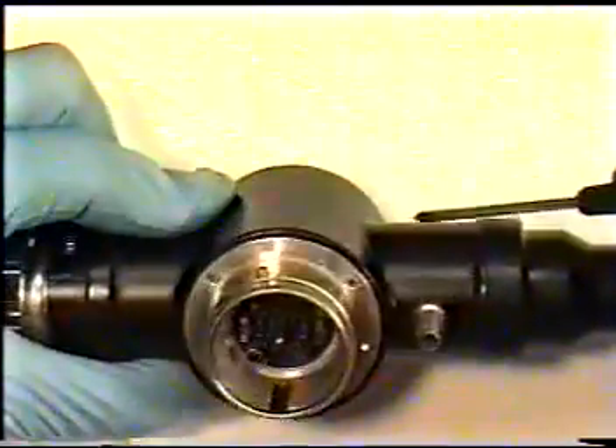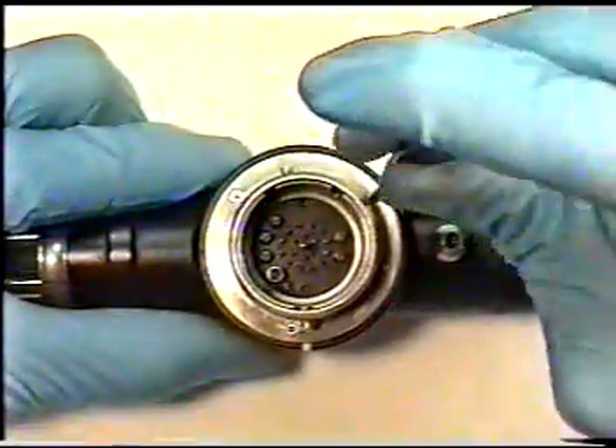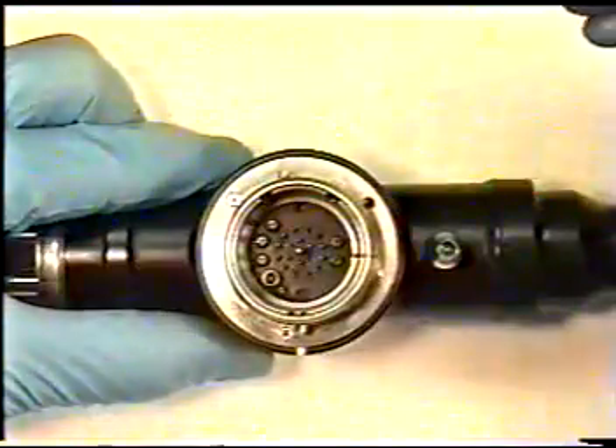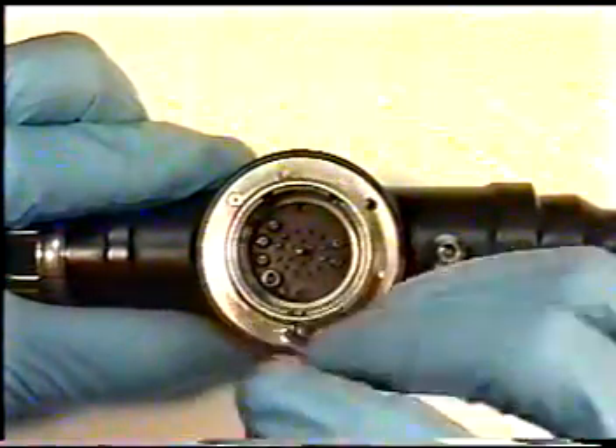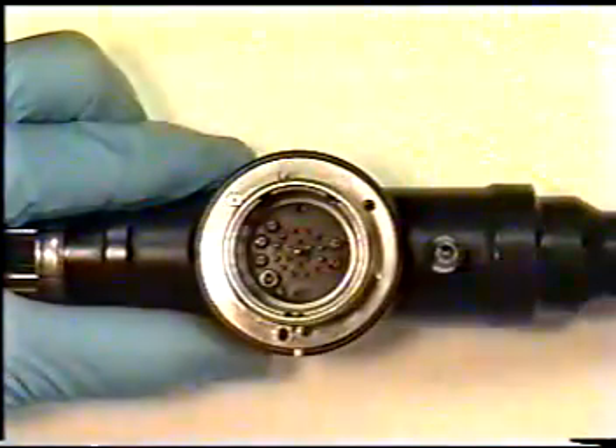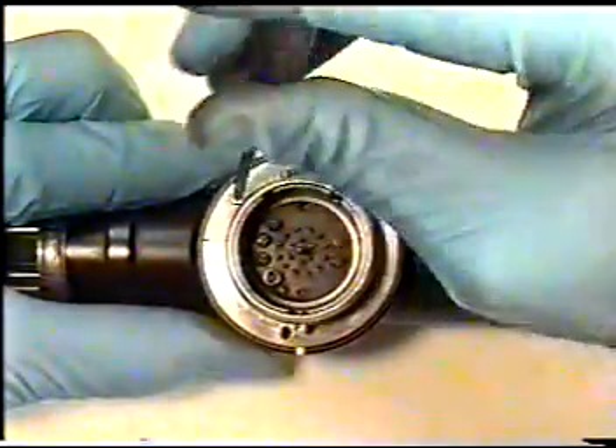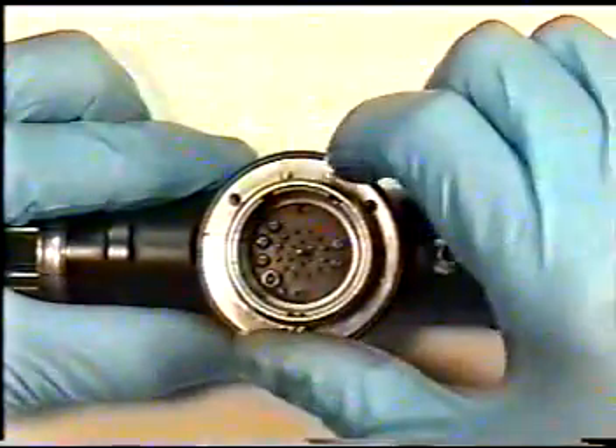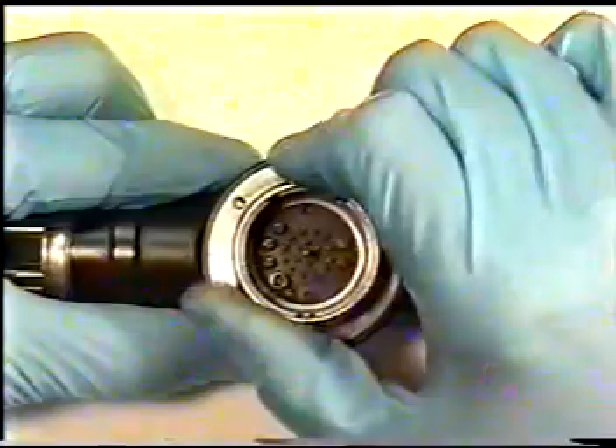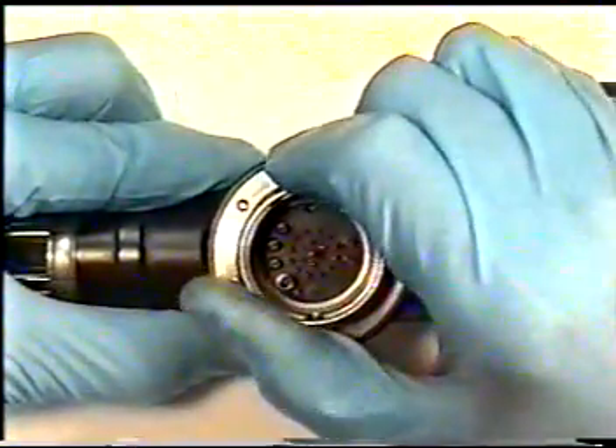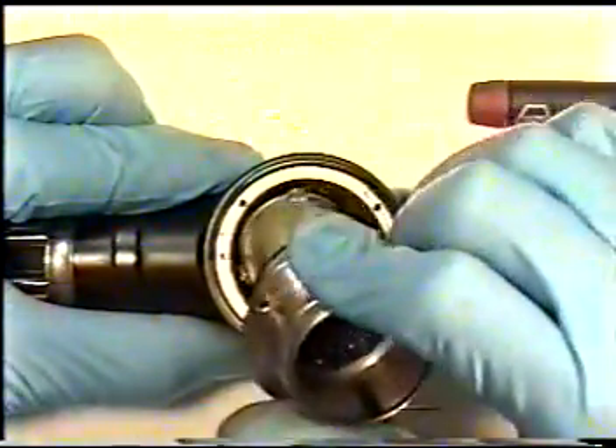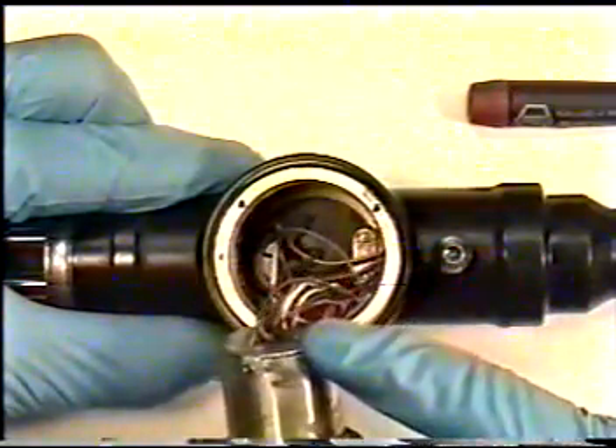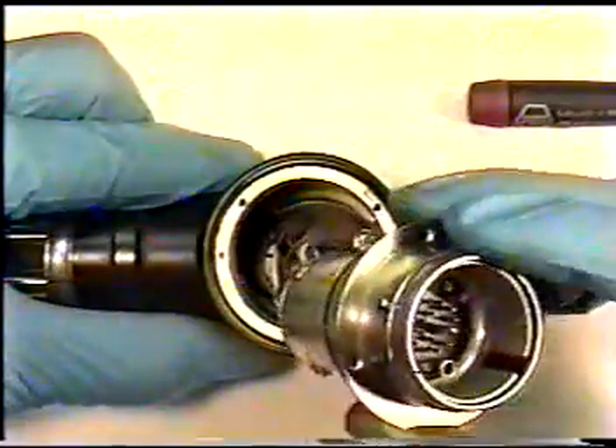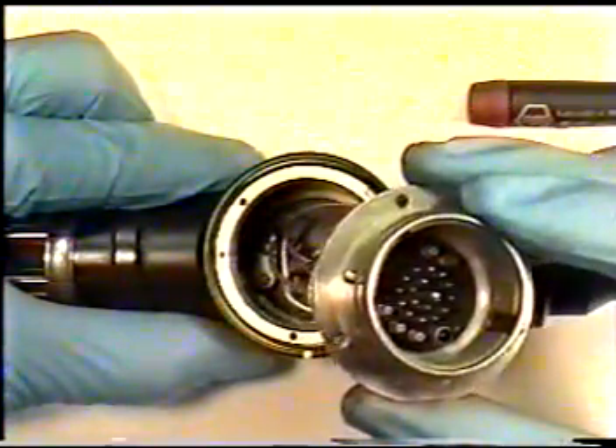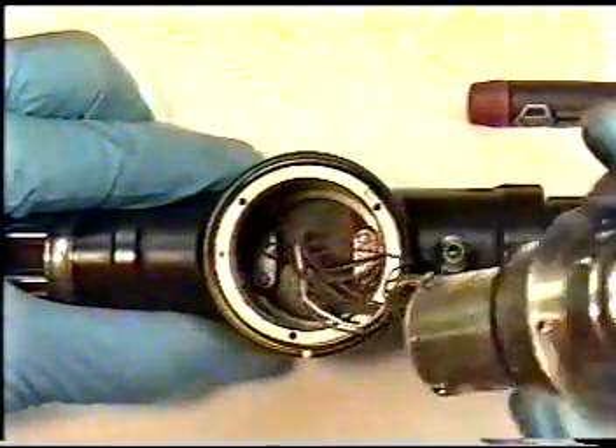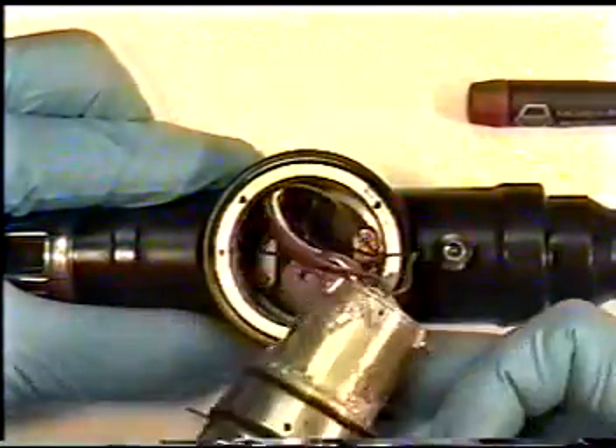From the light guide connector body section, there are 3 stainless steel screws. Remove these screws and retain for reassembly. Being extremely careful, rock your video connector back and forth and carefully pull and lift out without pinching or cutting any of the CCD wires. Do not touch any of the pins internally in the connector because static may damage the CCD assembly. Pull your CCD connector to one side.